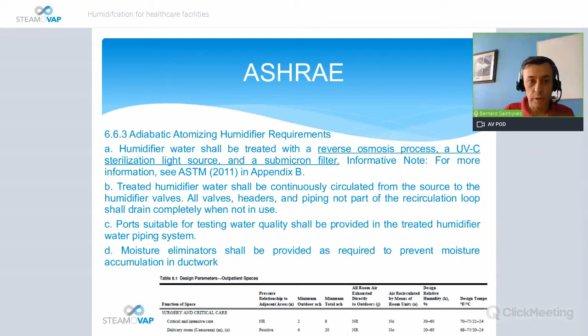As I said, the good point is that relative humidity is one of the 7 most important design parameters from this famous table in the ASHRAE standard. But it is disappointing that for most of the healthcare spaces, there is no range specified or indicated, and only an upper limit of 60 or 70% relative humidity. The impact of low relative humidity is very clear now for everybody. Let's hope that the next edition of the standard will be updated to be more specific on humidity level per space.